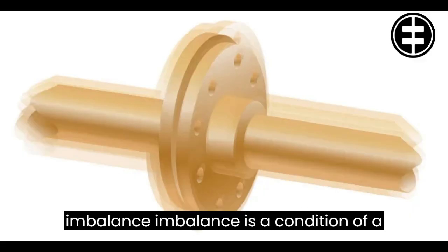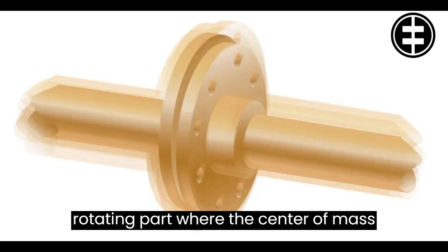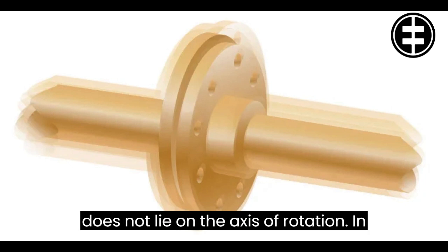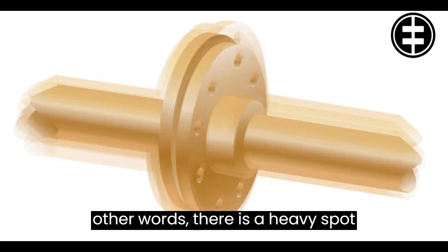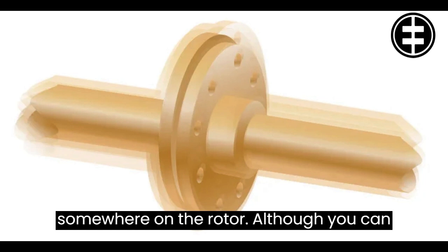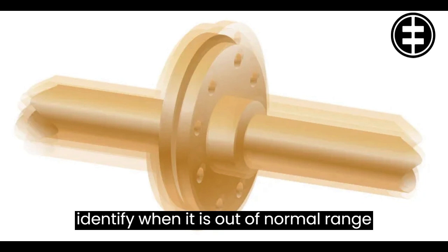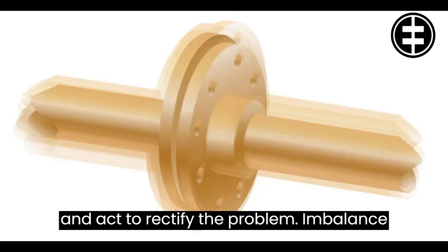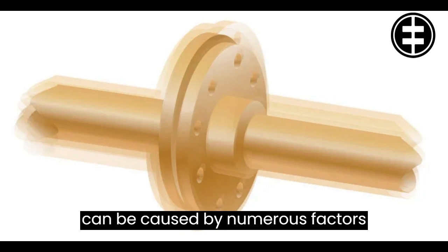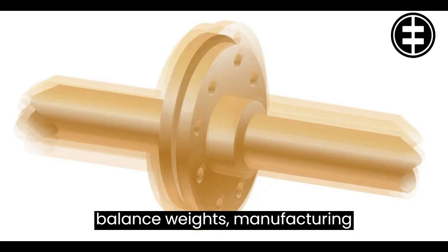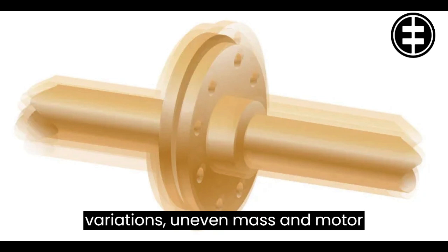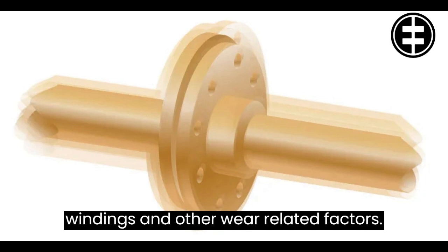8. Shaft imbalance. Imbalance is a condition of a rotating part where the center of mass does not lie on the axis of rotation. In other words, there is a heavy spot somewhere on the rotor. Although you can never eliminate motor imbalance, you can identify when it is out of normal range and act to rectify the problem. Imbalance can be caused by numerous factors including dirt accumulation, missing balance weights, manufacturing variations, uneven mass in motor windings, and other wear-related factors.